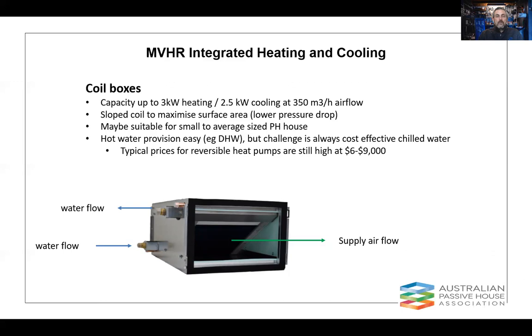Hot water supply for these is fairly simple because we've got domestic hot water obviously, but the challenge at this point is chilled water for that sort of product. Now reversible heat pumps are available in the market, but they're still fairly expensive, and it's, I guess, unclear whether they're going to fall much in price given time, but a little bit of market research has suggested that you're probably looking at anywhere from $6,000 to $9,000 for a reversible heat pump that could give you chilled or hot water. And it's interesting to note that those capacities there are really at the low end of reversible chillers.